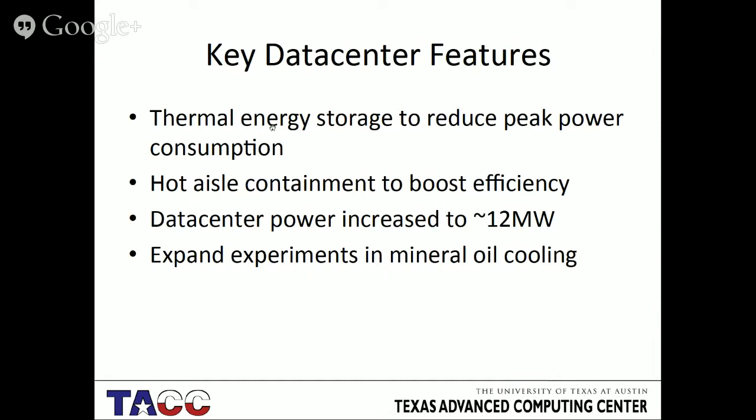Basically what I just said. I'll mention the last item there about the mineral oil cooling. We have a partnership with a company called Green Revolution, and we have a couple of containers which are similar to a rack in which you can put computing equipment into mineral oil. So the advantage of cooling with mineral oil is it has a much higher heat capacity, so the mineral oil only has to get down to about 100 degrees Fahrenheit because that's still cooler than the chip, and it can keep the chip cool enough to run. So it's much cheaper to cool things with mineral oil, although I'll tell you it's a lot messier.